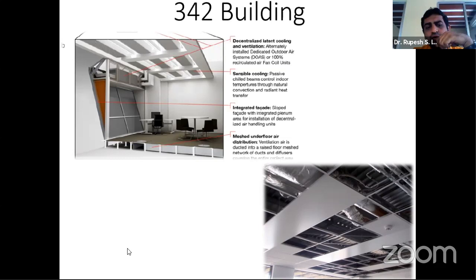The 342 building again was, I would say, a high performance building. It was not net zero energy, but there were a lot of parameters like sensible cooling through radiant cooling, and there was an integrated facade with an underfloor air distribution which was meshed into it. In this building, there was also a false ceiling, and the false ceiling itself acted like the radiant panel. So it was an active false ceiling rather than a non-active false ceiling. All of those tiles that you see here were radiant panels. So that would be my air conditioning system itself, which almost achieves 700 square feet per ton in terms of the heat load requirement itself.